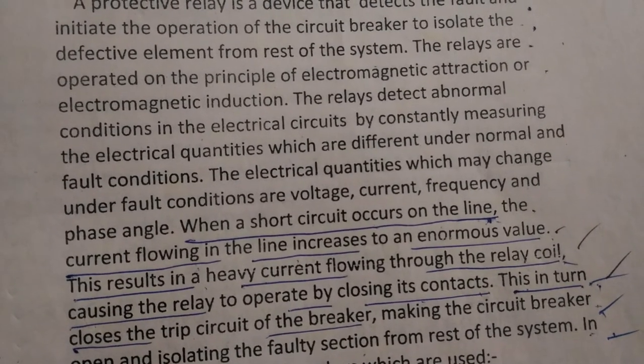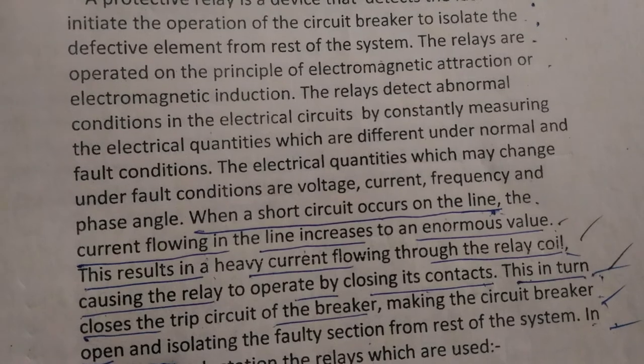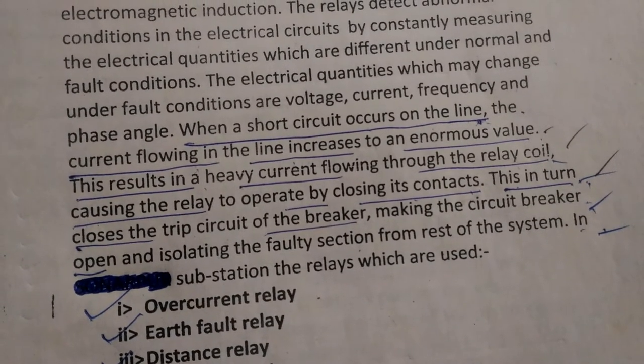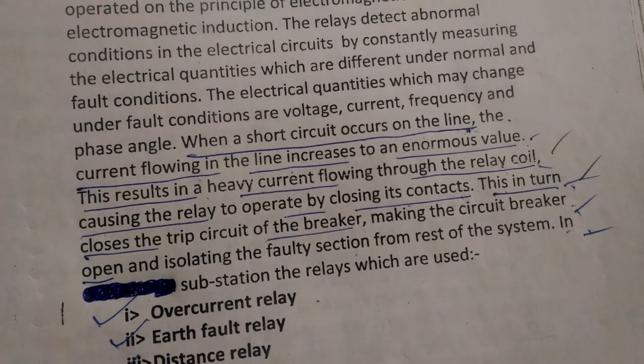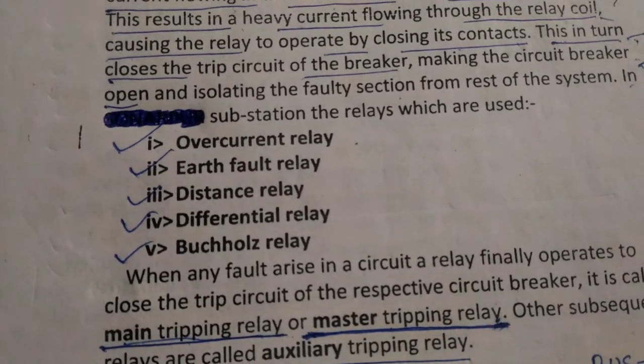The electrical quantities which may change under fault conditions are voltage, current, frequency, and phase angle. When a short circuit occurs on the line, the current flowing in the line increases to an enormous value, causing heavy current to flow through the relay coil, causing the relay to operate by closing its contact. These in turn close the trip coil of the circuit breaker, making it open and isolating the faulty section. The relays generally used in substations are overcurrent relay, earth fault relay, distance relay, differential relay, Buchholz relay, and oil surge relay.